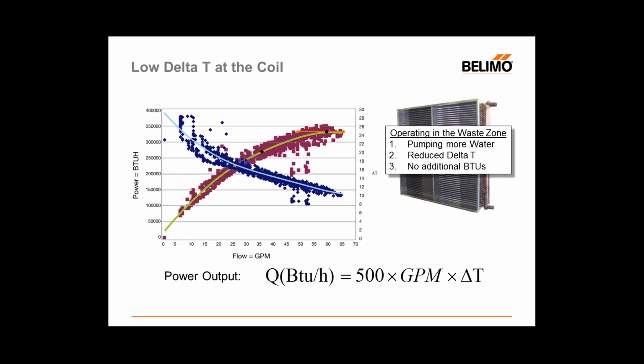So let's go take a look at a partial load point. Now, even on this particularly clean and concise data cloud of points, we can still draw a horizontal line across a pretty wide sweep of flow rates that produce the same amount of cooling in that space. And so even at lower loads, we can violate delta T and use less flow to create the cooling required. So this is a little hard to illustrate on this graph.